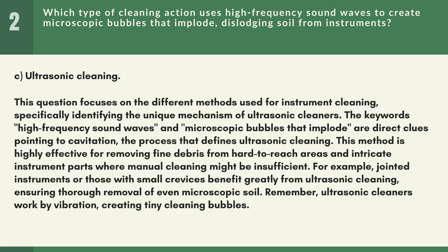This method is highly effective for removing fine debris from hard-to-reach areas and intricate instrument parts where manual cleaning might be insufficient. For example, jointed instruments or those with small crevices benefit greatly from ultrasonic cleaning, ensuring thorough removal of even microscopic soil. Remember, ultrasonic cleaners work by vibration, creating tiny cleaning bubbles.